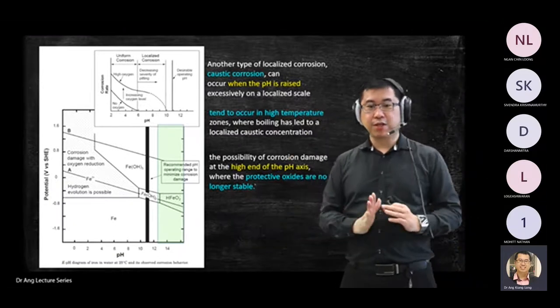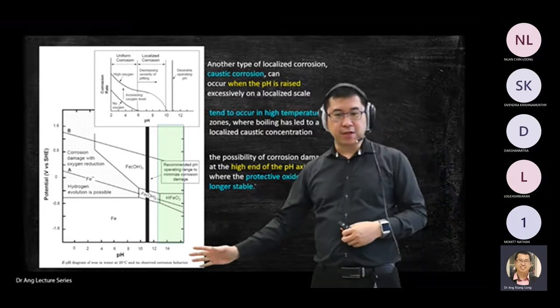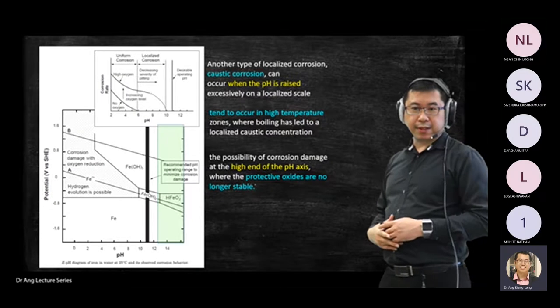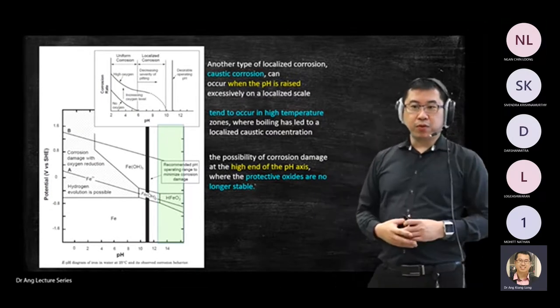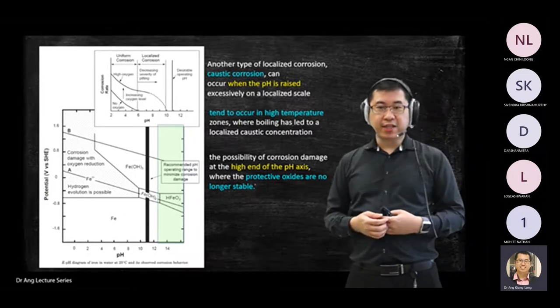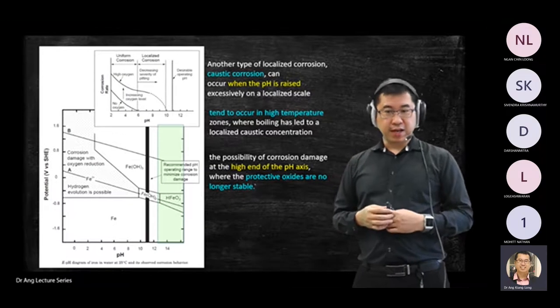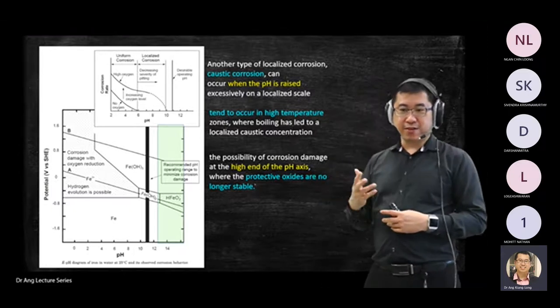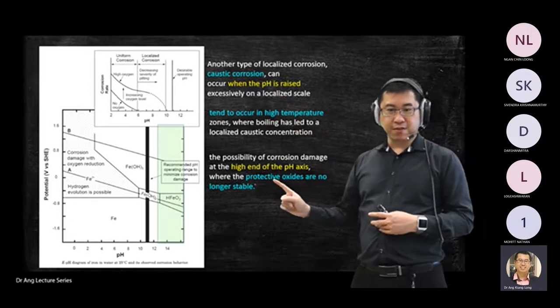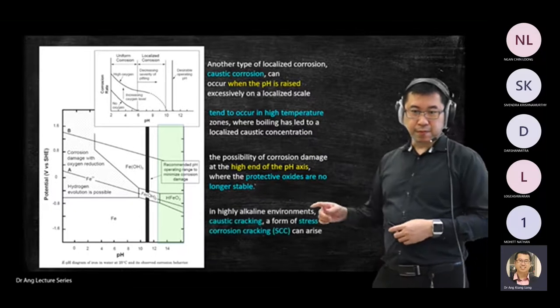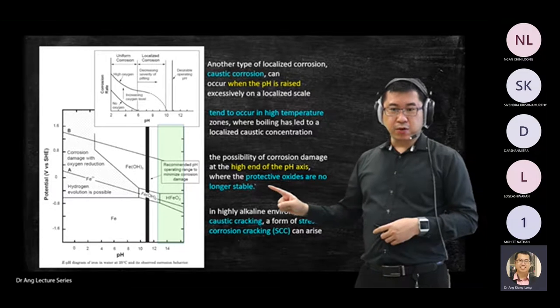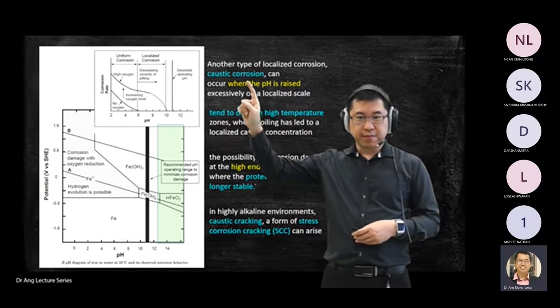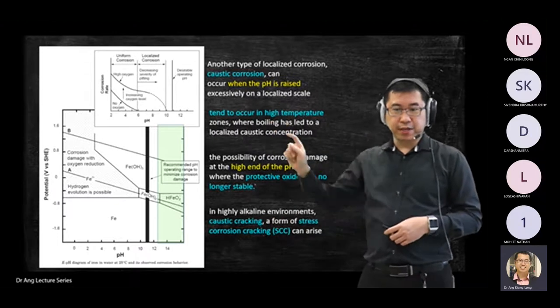I want you to understand what happens if you reduce or increase the pH based on the potential versus pH diagram. If you increase the pH too high until it becomes too alkaline, the protective oxide layer is no longer stable or dissolves, and a new type of corrosion called caustic corrosion will happen, causing cracking.